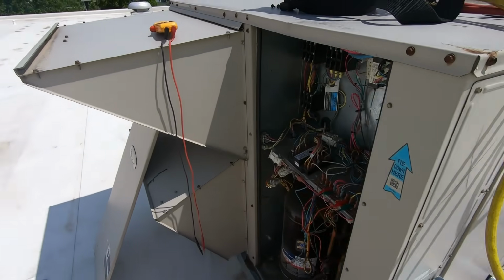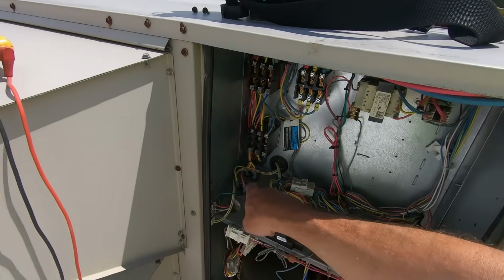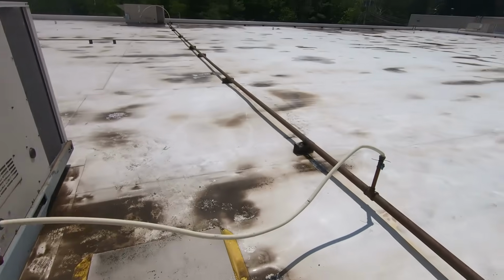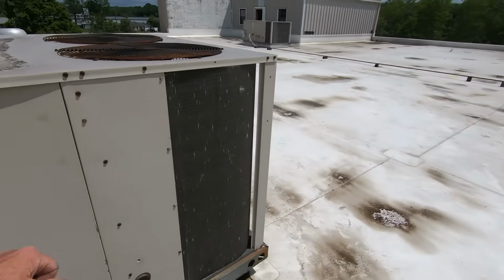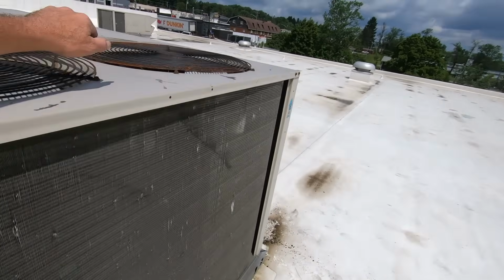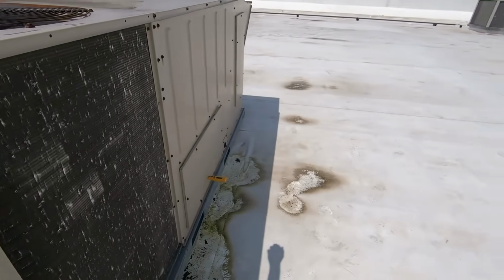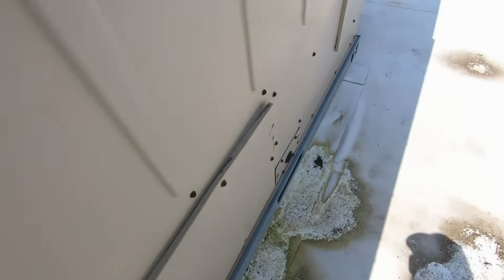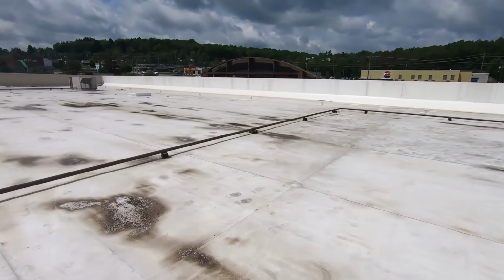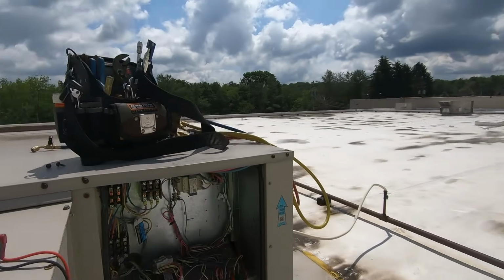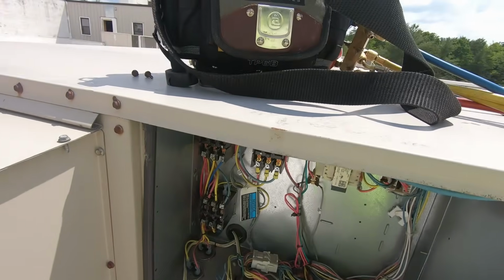All right, so found a weak capacitor on one of the condenser fan motors. They are both running. It was reading 13 on a 15 UF. I'm gonna write up the capacitor, 54 degrees. I'm gonna go ahead and mark that capacitor, that way if somebody else comes, they don't have to do any thinking.